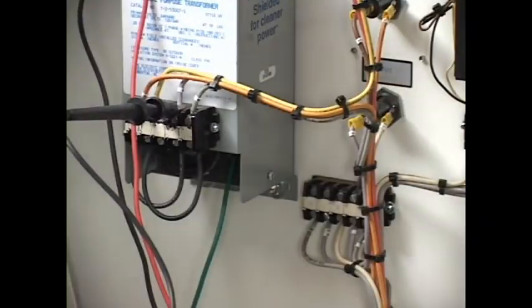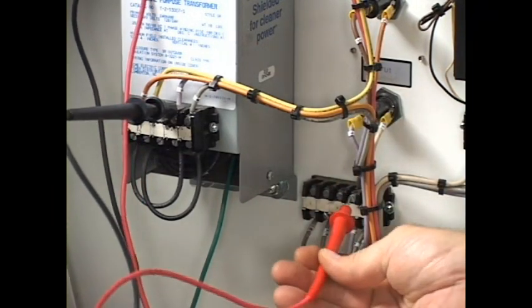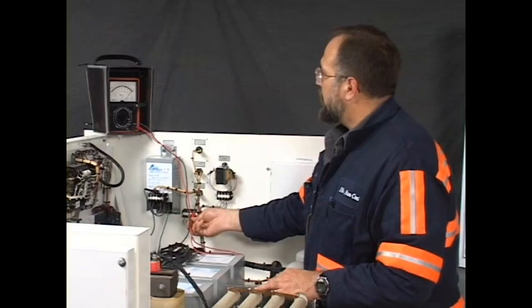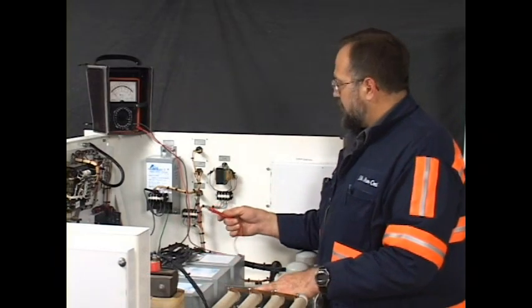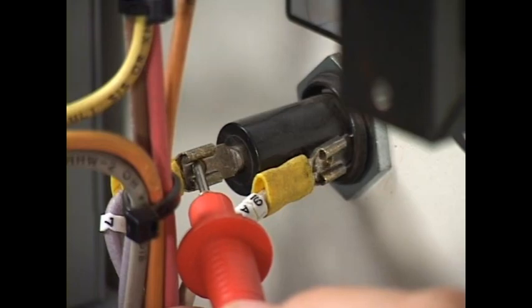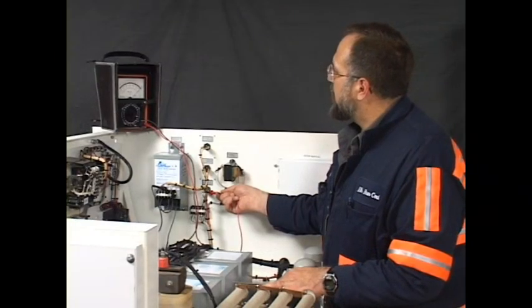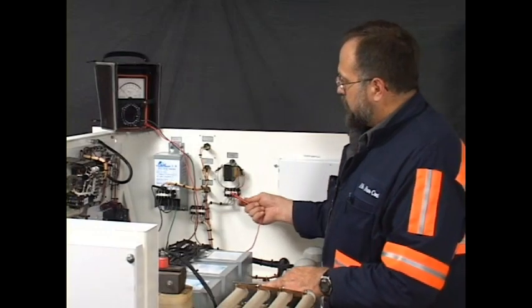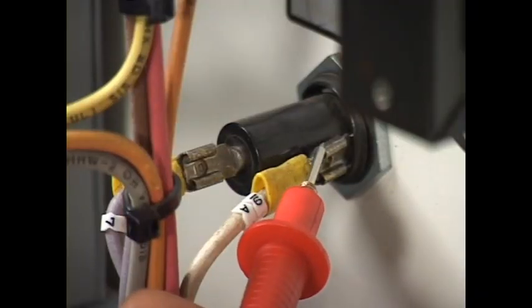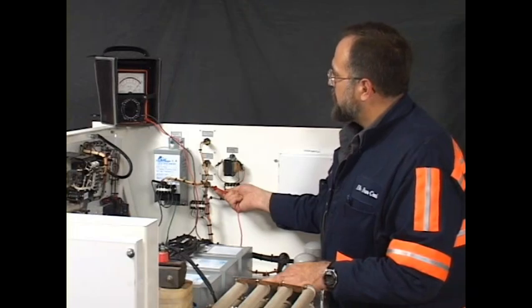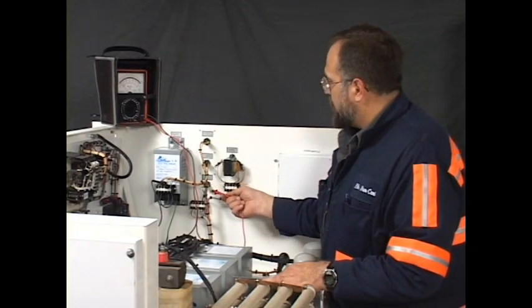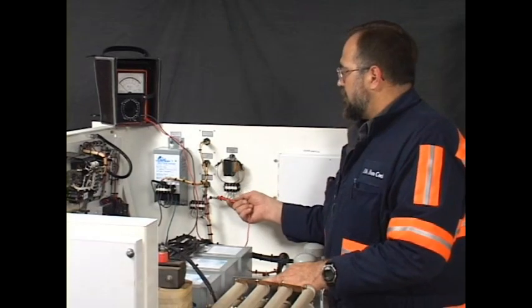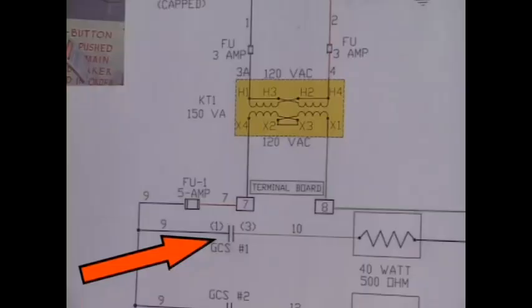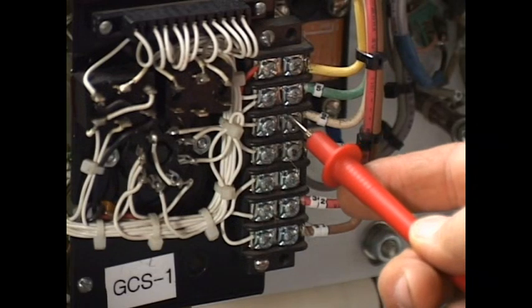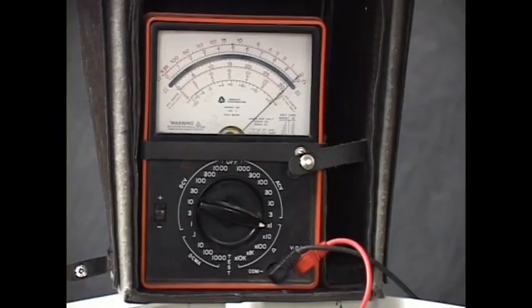I'm clipped on 7. The problem states that we had proper control voltage on the secondary. I have continuity to the terminal board, wire 7. I'm checking to the back of FU1, the line side. I have continuity there. I'm going to check through FU1. The fuse is good, not open or blown. At this point, it changes to wire number 9. The next point where we can read wire number 9 from the fuse is GCS1, contact 1. Here's wire number 9, and indeed it's good.